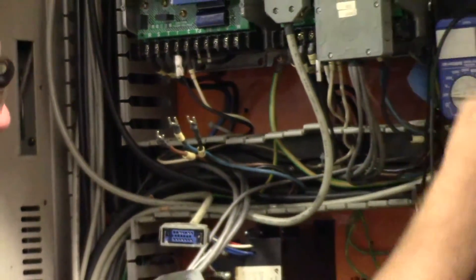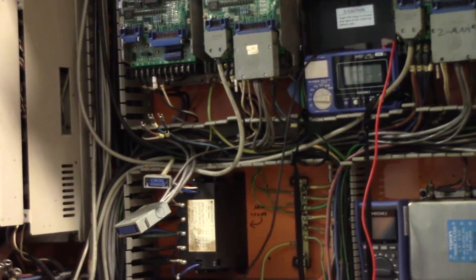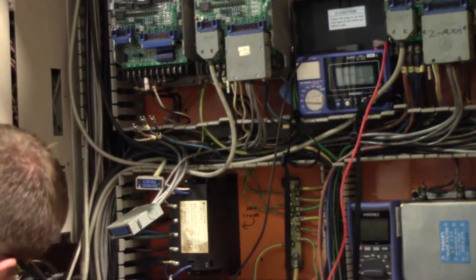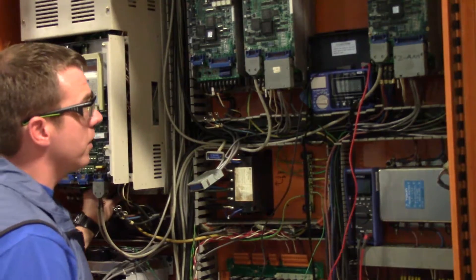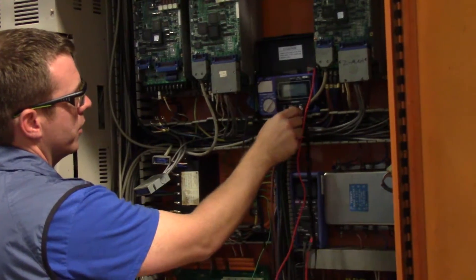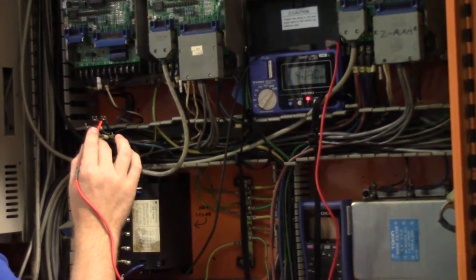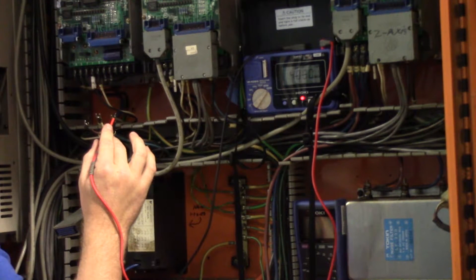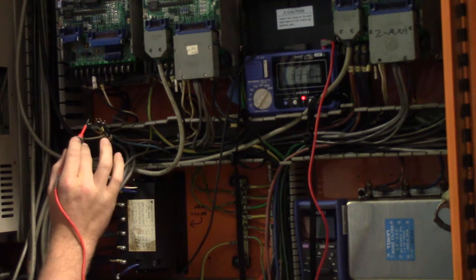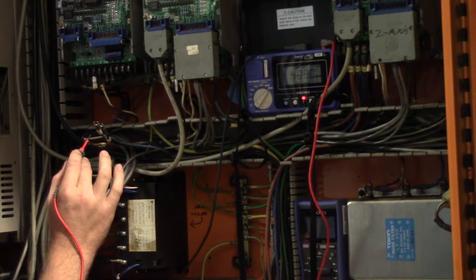Now we're going to move on to our insulation tester, our digital mega ohm meter or megger. This is our Hioki IR 4056 and you have to find a suitable ground. I used the cabinet ground underneath the spindle drive. So we'll turn it to a thousand volts. Remember we always use a thousand volts when we're checking for insulation. Let's check W. We're at four thousand. Check V. We're at four thousand and we'll check U.